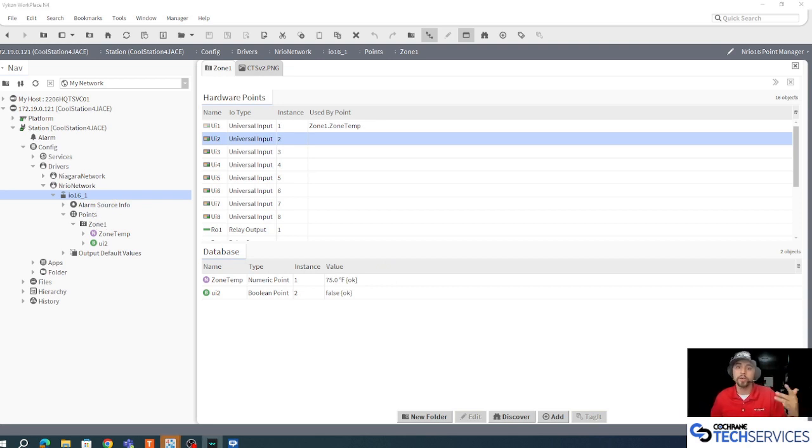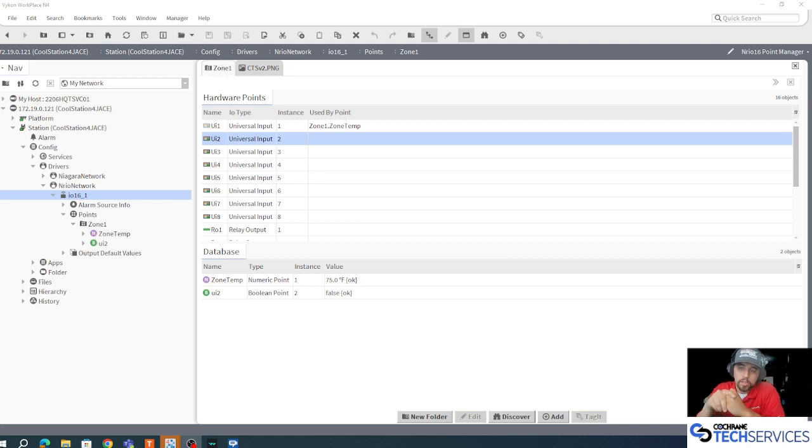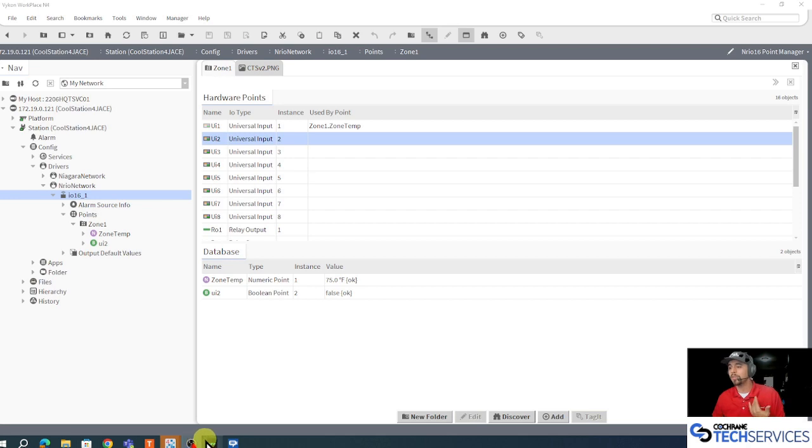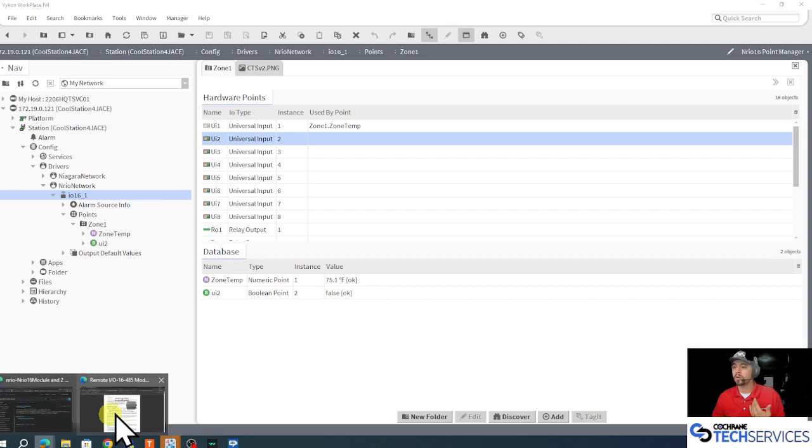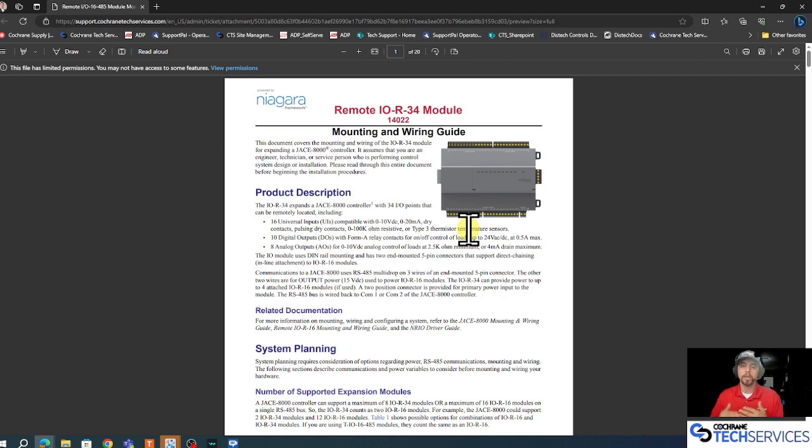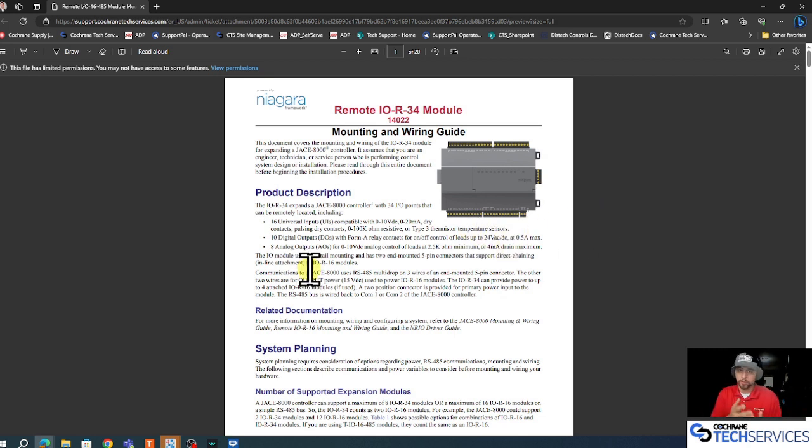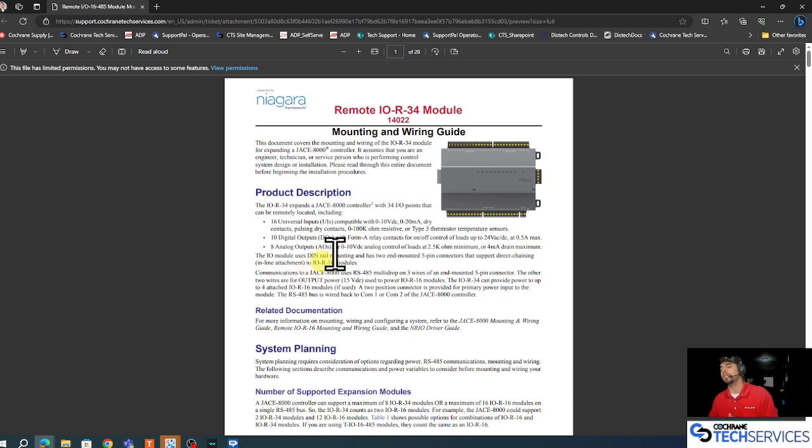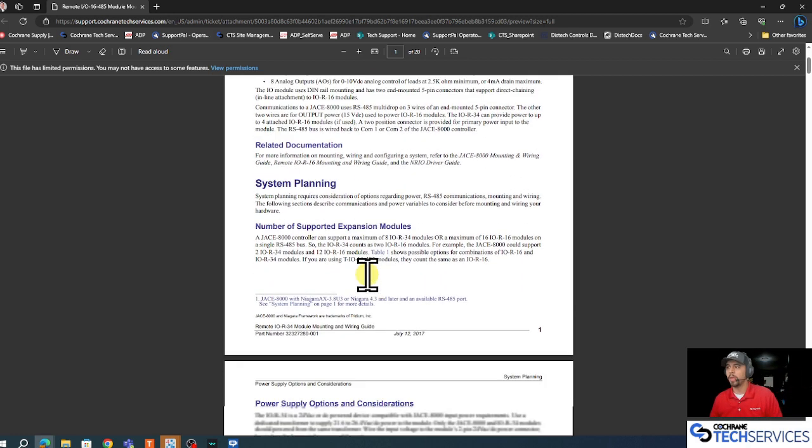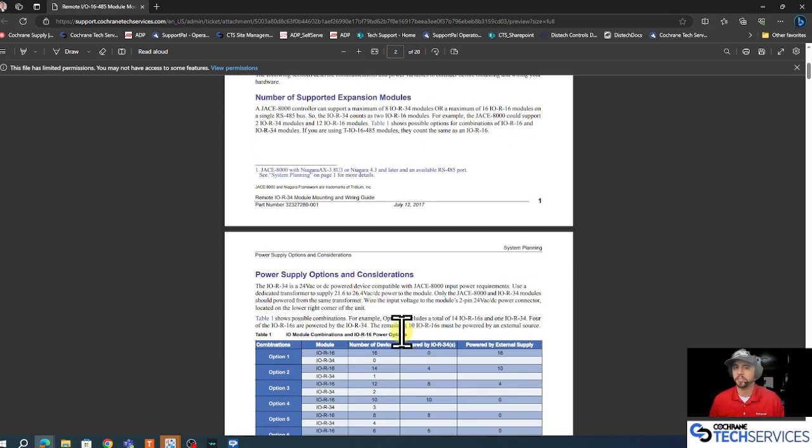Yeah, a couple other things to keep in mind: an IO 16 is considered one device where an IO 34 is actually considered two, and we can have up to 16 NRIO devices per JACE 8000. So what does that mean? That means we can have eight IO 34 devices or 16 IO 16s. Now we can also mix and match here, maybe we want four 34s, right? That would consume eight devices of our 16 available. There are all kinds of different configurations we can do here.